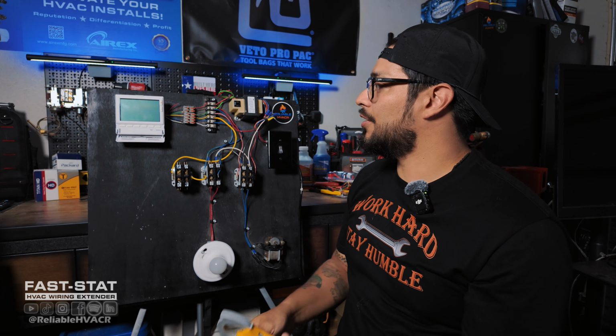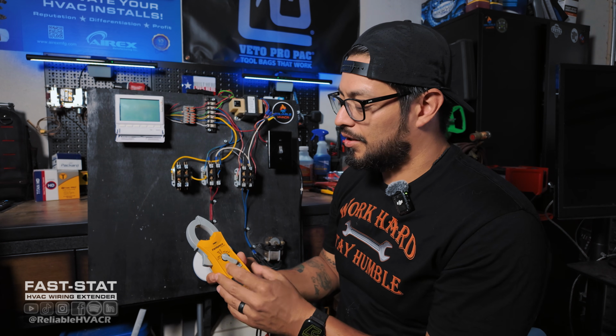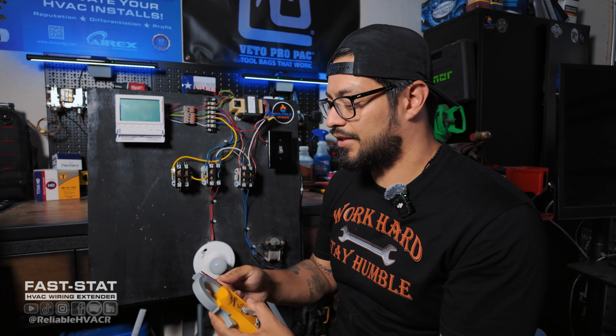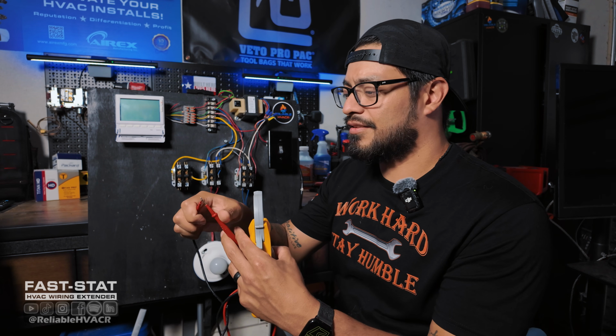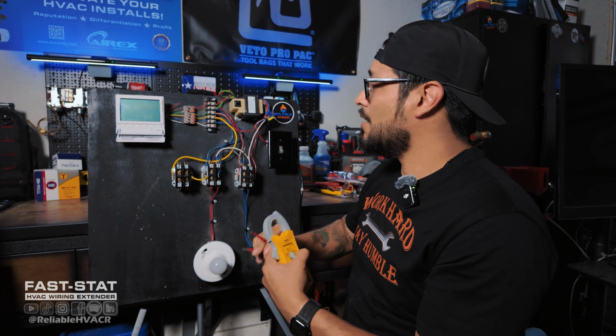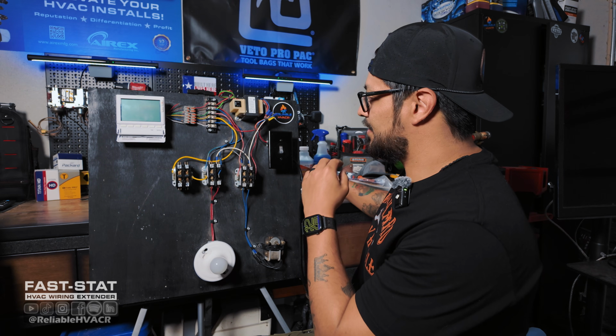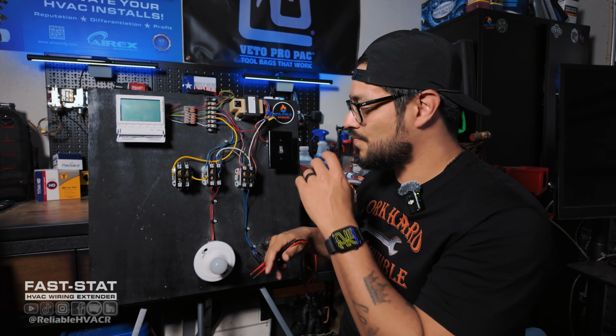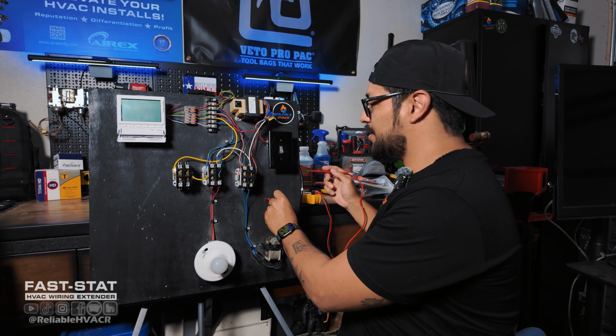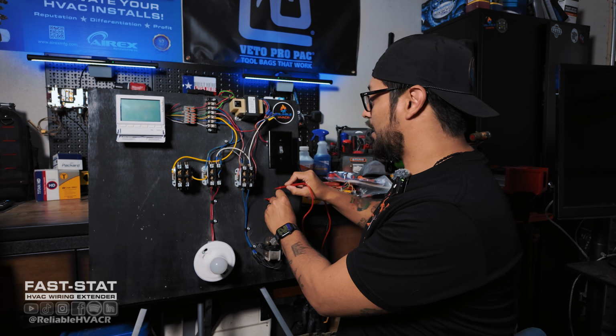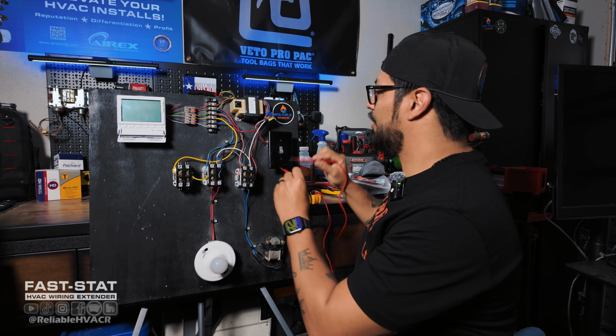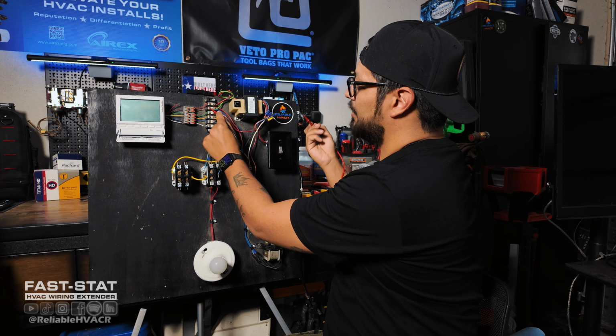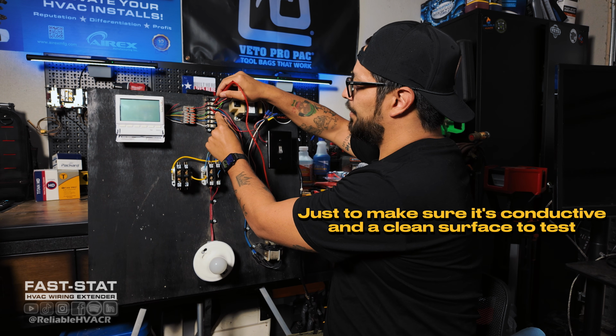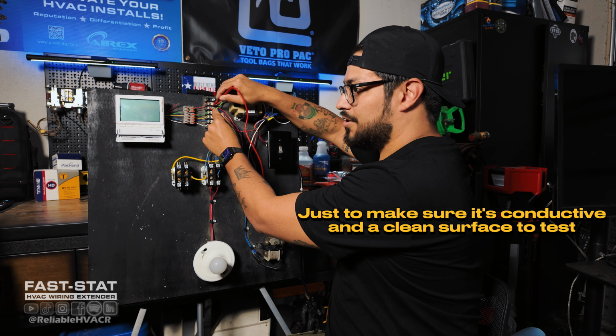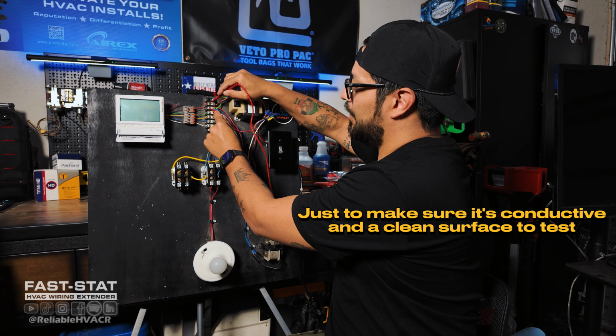So the easiest thing you can do, if you do have a short, let's say you did pop a fuse or transformer, is go over to continuity. You can also check resistance. We'll talk about that in a minute. But always test your leads. Make sure you get that tone. Another thing that I do is check whatever ground I'm using. If this was a panel and I'm going to use that as my ground to check to each terminal, I'm going to check that first. I don't think I have a metal panel here, but I'll use common as an example, where I'm going to check to common. I'm going to put my lead on that panel or screw also and make sure that I get a tone first. And then I'm going to start checking each one.